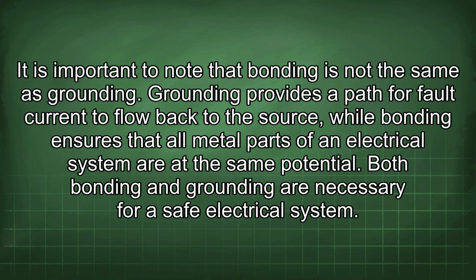It is important to note that bonding is not the same as grounding. Grounding provides a path for fault current to flow back to the source, while bonding ensures that all metal parts of an electrical system are at the same potential. Both bonding and grounding are necessary for a safe electrical system.